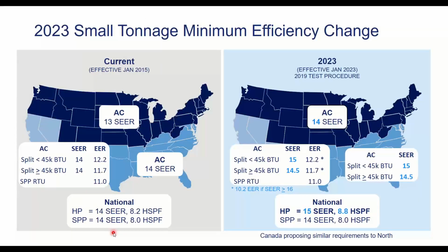So for the small stuff, mostly residential guys would care about this, or if you're putting in split system single phase stuff, or small rooftops like 3-4 ton units - the current is 13 SEER minimum. The new one in 2023 will be 14 SEER minimum for where we live - meaning Illinois, Indiana, Michigan, Wisconsin, Minnesota, where most of you guys are from, Missouri, Kansas. If you're further south, you have a different set of rules, significantly more confusing and complicated, but the north is easy: 13 SEER goes to 14 SEER. If you're in the south, like Georgia for example, you're already at 14 SEER, and now you have to go up to either 14.5 or 15, depending on the size of the unit. Not confusing at all.